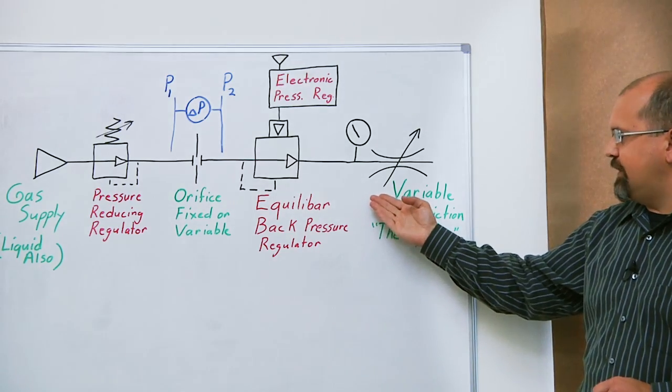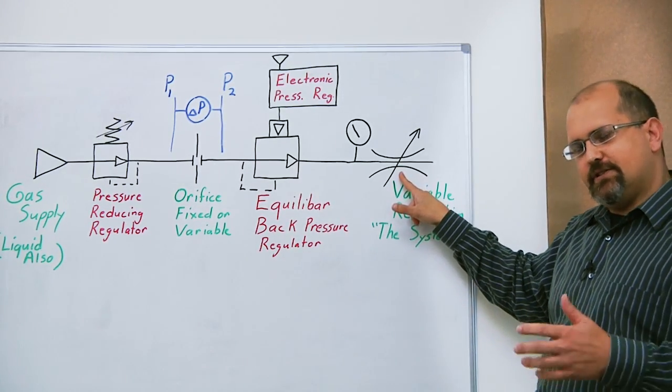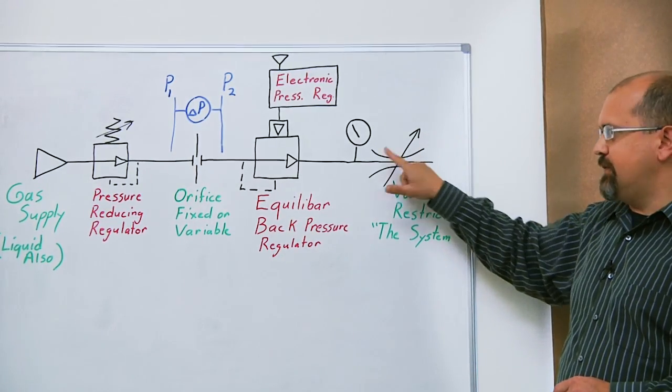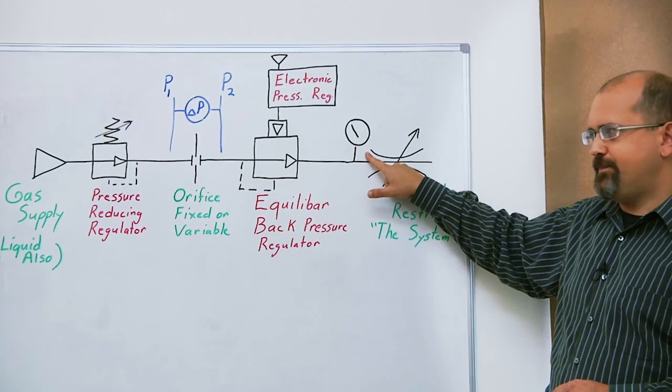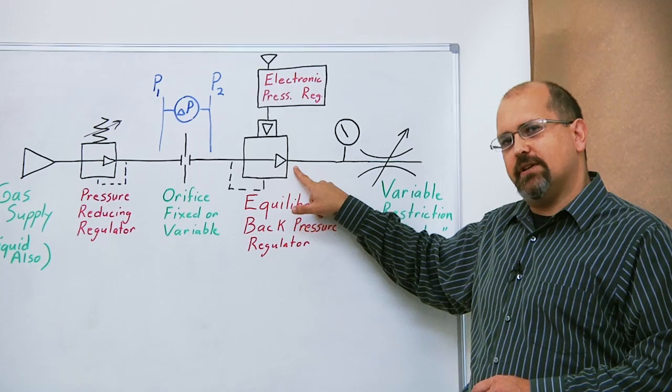So regardless of variations in the system—here I've shown the system as a variable orifice, but anything that's variable going on in the system which would change the system pressure—is sensed and automatically compensated for by the back pressure regulator.